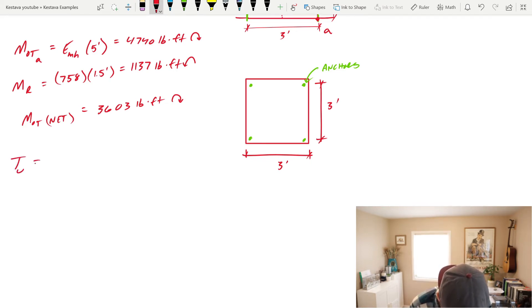To find your uplift, Tu, that would be your net overturning moment divided by whichever way you're looking at it. And we're looking at demand moving from left to right. So your couple would be this three feet, which would then get you tension on those two anchors and compression on those two anchors. Tu equals your net overturning moment divided by your couple of three feet divided by two anchors, which gets us 601 pounds, which we'll circle, per anchor.